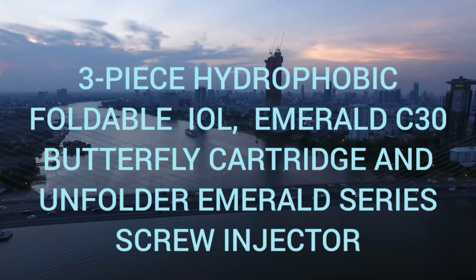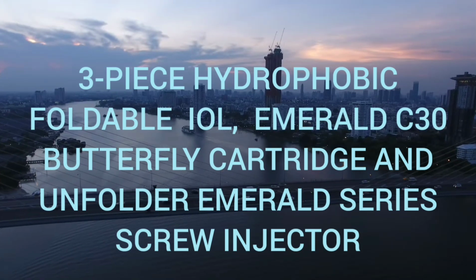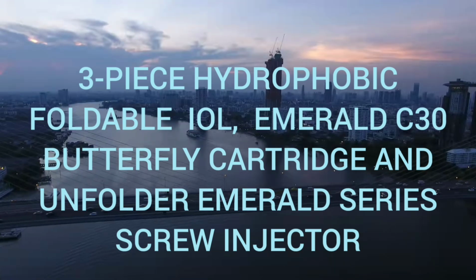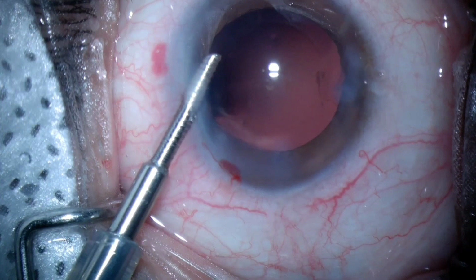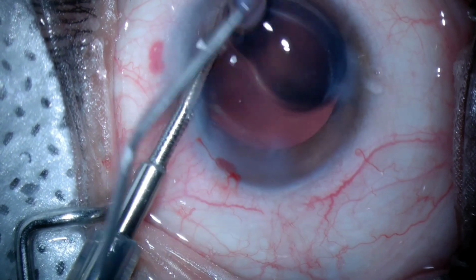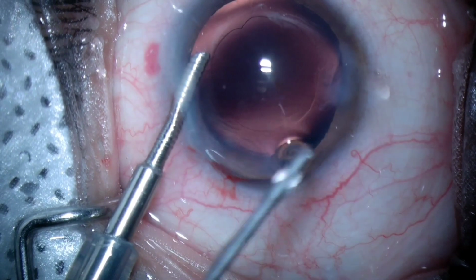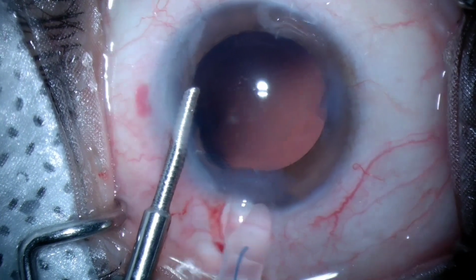3-piece hydrophobic foldable IOL Emerald C30 butterfly cartridge and unfolder Emerald series screw injector. The cartridge 2.8 mm lumen size necessitates a corresponding corneal incision. Begin by securing the IOL at the distal end of the cartridge within its case as demonstrated. Slide the IOL into the cartridge groove, aligning it with the image on the leaf. Securely fold the leaves and load the cartridge onto the Emerald injector.